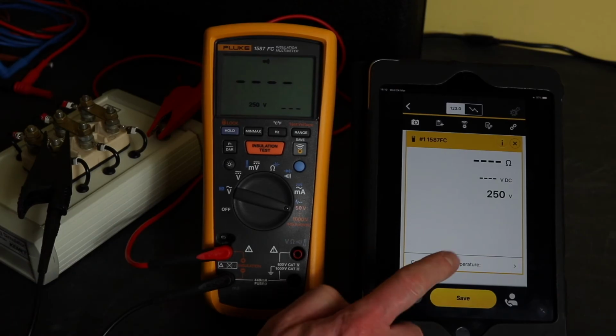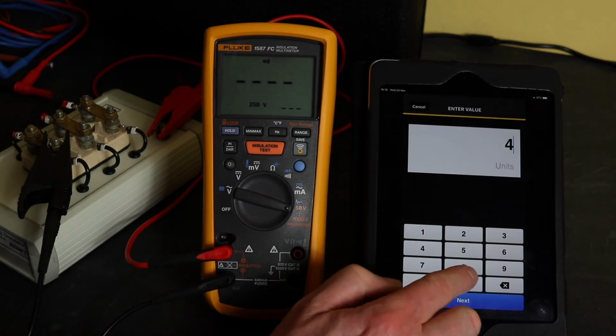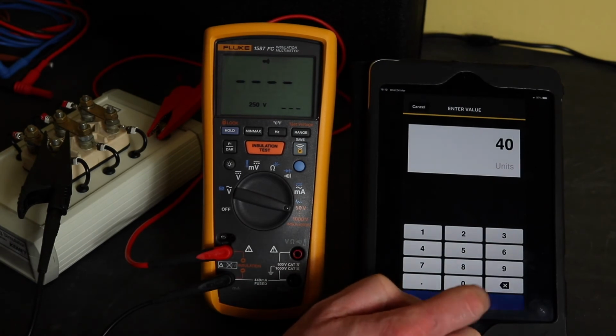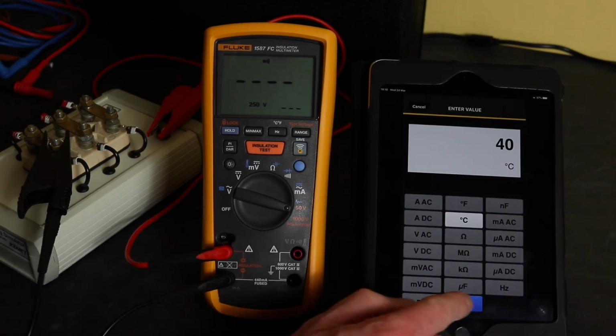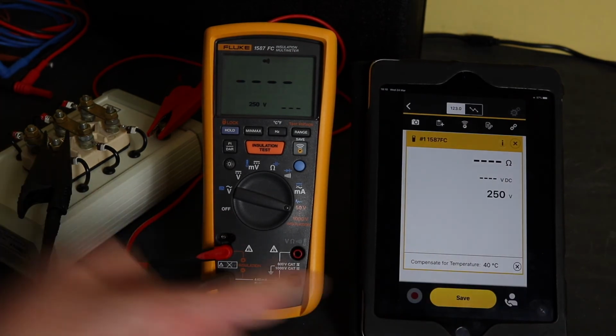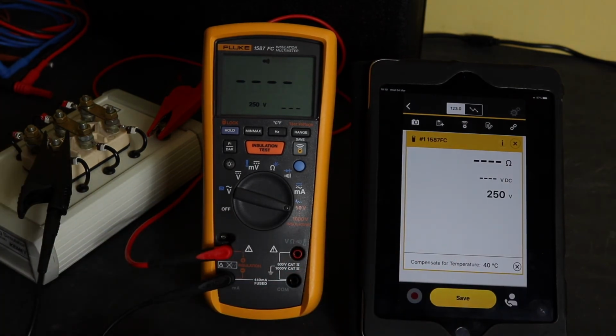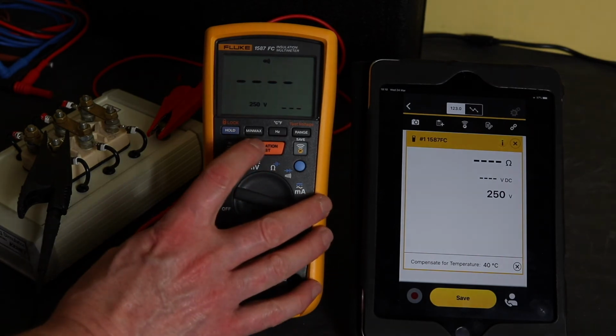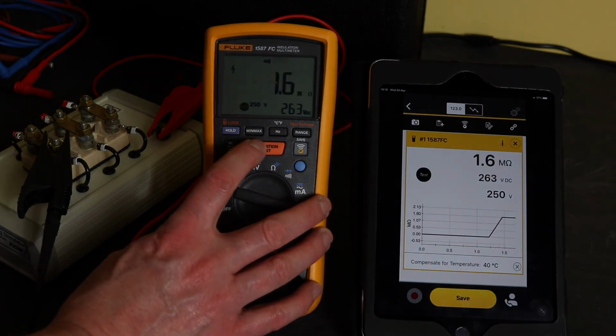Now, the Fluke does have a temperature compensated facility as well, again just for the spot test, but to be able to do that, you do have to have it connected to the iPad, and then the functionality appears, whereas with the Megger it's actually built into the instrument.